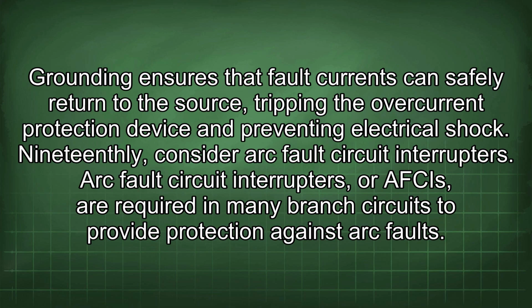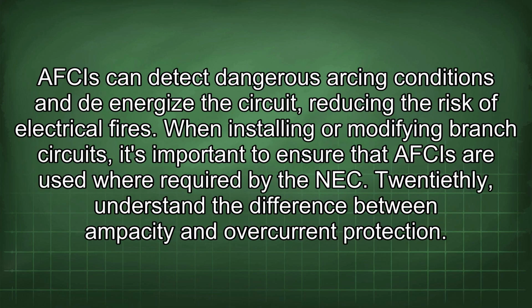19thly, consider arc fault circuit interrupters. Arc fault circuit interrupters, or AFCIs, are required in many branch circuits to provide protection against arc faults. An AFCI can detect dangerous arcing conditions and de-energize the circuit, reducing the risk of electrical fires. When installing or modifying branch circuits, it's important to ensure that AFCIs are used where required by the NEC.